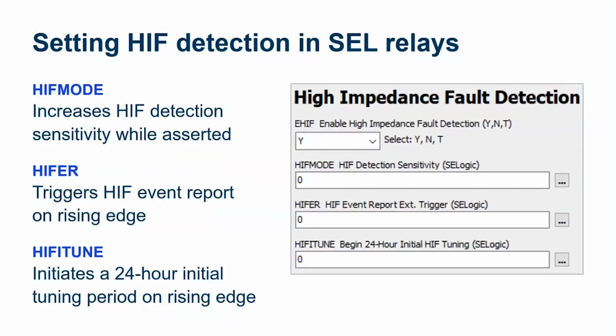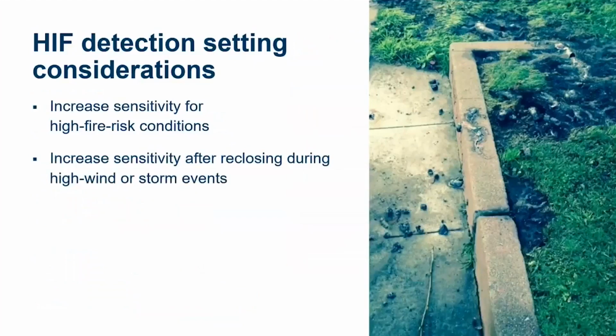And then we have HIFITUNE. This SELogic equation, on a rising edge, will trigger a new initial 24-hour tuning period. This allows us, if we have a significant change in the configuration of our circuit or the type of loading we have, to manually or automatically initiate a new tuning period using this equation. So when would we want to potentially increase sensitivity? We looked at the HIF mode setting, and we talked about having the ability to increase our sensitivity using that.